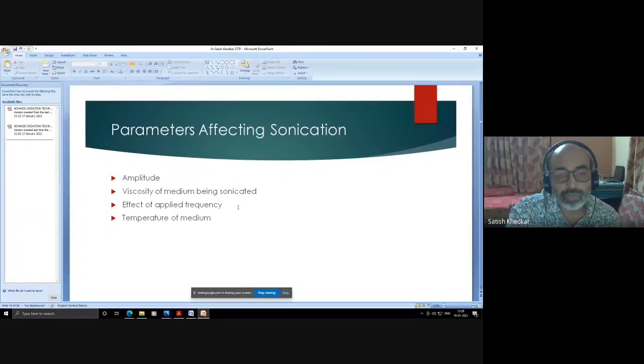Then temperature of the medium. Temperature and viscosity are interrelated. The higher the temperature, the lesser the viscosity. So as the temperature of the medium increases, the viscosity will go on decreasing. So initially, if there is load shown by the meter, then gradually after some time, because of the higher temperature in the medium, the viscosity will go on reducing, and the load on the transducer will be reduced and shown by the meter. You can verify these facts while performing experiments with the sonication instrument.